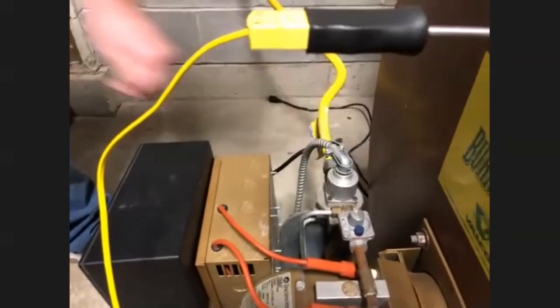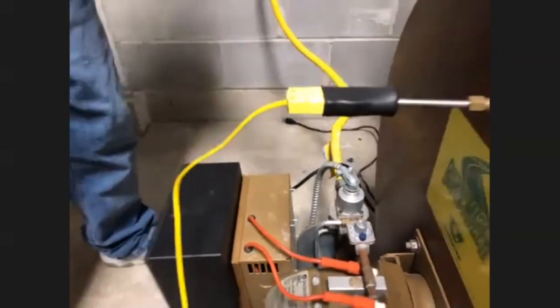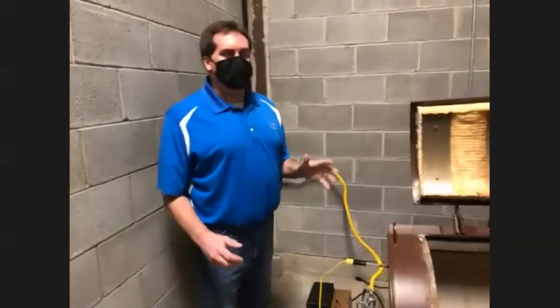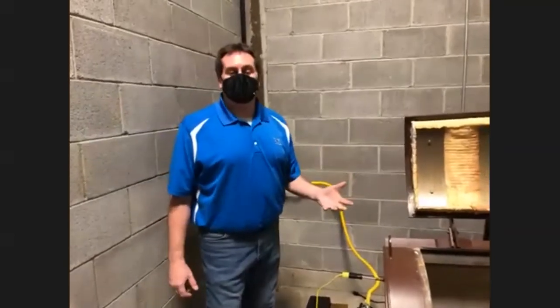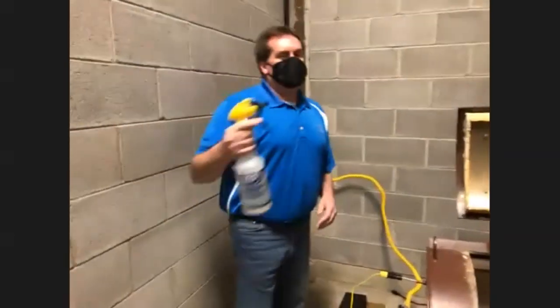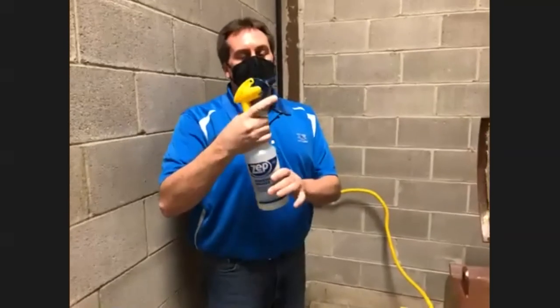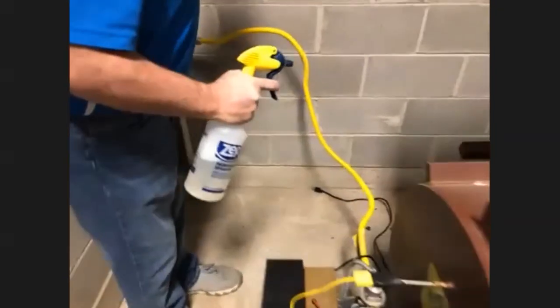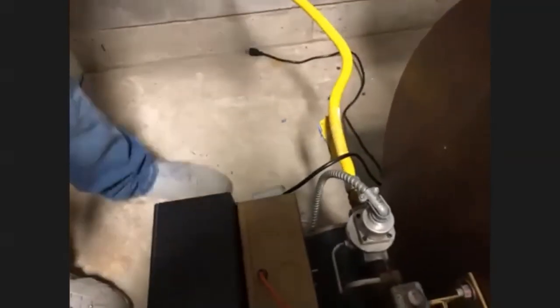And when you do set these up, again, with any gas component, you want to make sure that when you do any gas connections, you do a leak test. Normally that's just a soapy water solution. You spray that on your connections, I'll turn the gas on, and if you have any leaks, you will get some bubbling. That's what the soapy solution does. So as you can see, we do not have that. So we have a good connection right there.